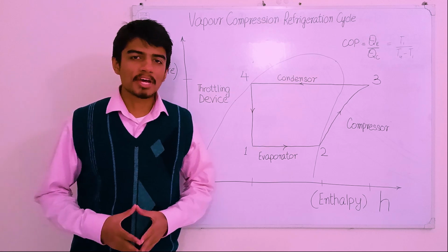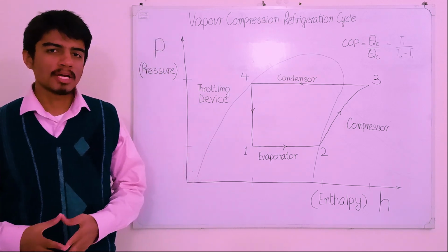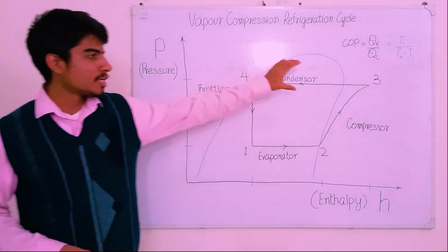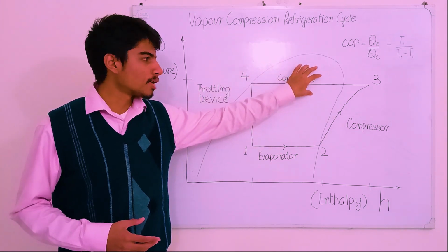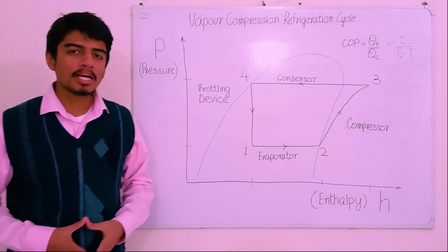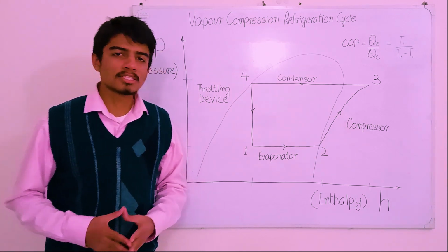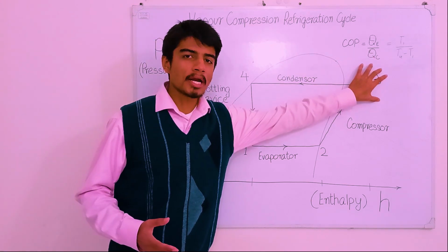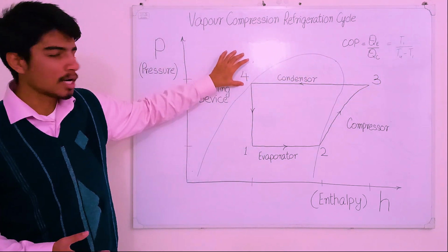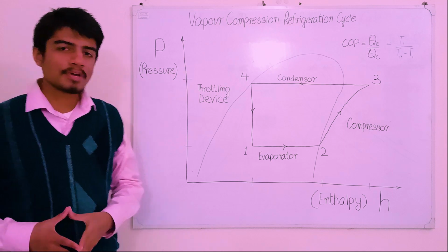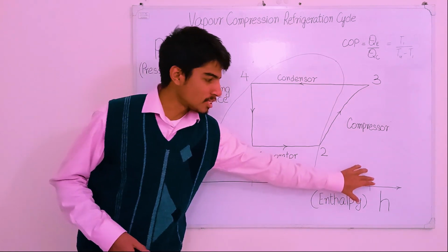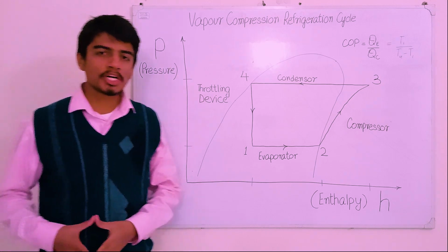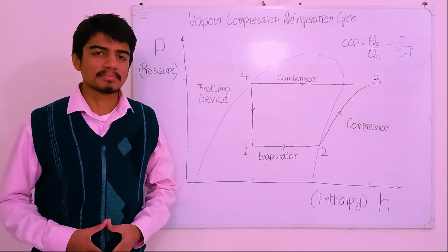In the condenser of air conditioner, heat exchange takes place between the refrigerant and the surrounding outside air. Refrigerant circulates inside the tubes of condenser. As a result of heat exchange, refrigerant releases its heat to the surrounding air and changes its phase from superheated vapor state to saturated liquid state. During this phase change, enthalpy of refrigerant decreases significantly while the pressure remains constant throughout the condenser.